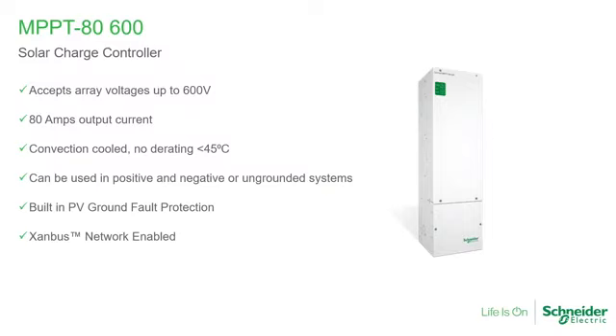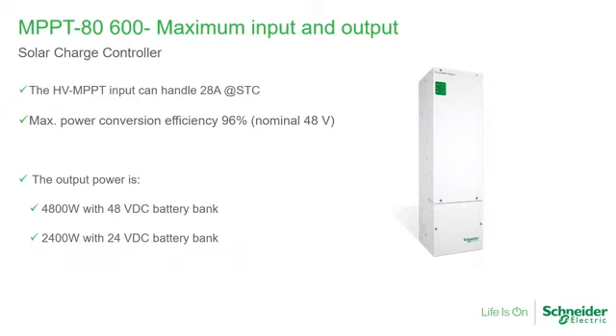It has a built-in ground fault, and because it communicates with all of the other Conext products, of course, it is a Xanbus device. Xanbus is our communication protocol. So this solar charge controller can actually talk to the Schneider inverters. And I will share with you later, as I'm talking about programming, some of the benefits, although it can work alone. So you may have a system that is DC only. It doesn't need an inverter to operate. So if you had maybe a system that is only DC, like in some telecom operations, this unit can operate without an inverter. But if the inverter is in the network, and if the inverter is a Schneider Electric inverter, then it can communicate, and we can actually monitor the performance through the monitoring and control platform, which is our Insight tool.